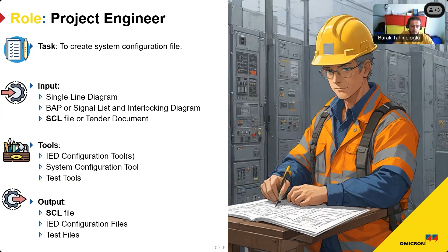Then later we would have the test tools to create the test files in office, and then we will execute this in the substation. The output of this work would again be an SCL file, but this time in a different format, plus the proprietary IED configuration files to be loaded to the IEDs. Finally, we would have the test files to be executed by the test set in the substation.